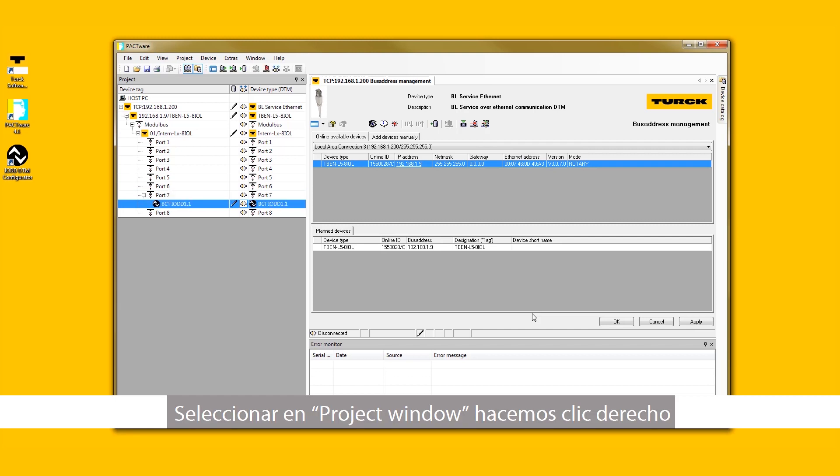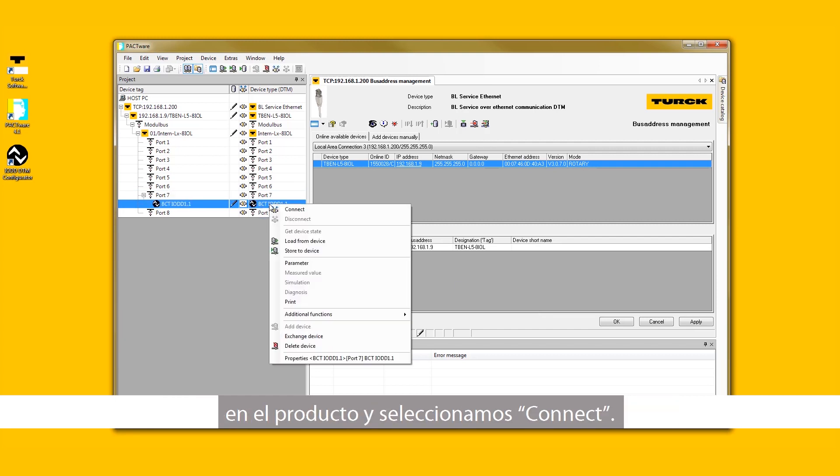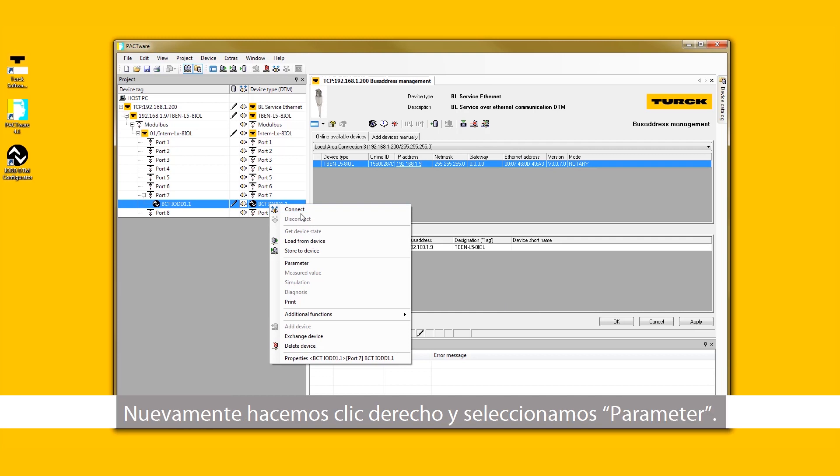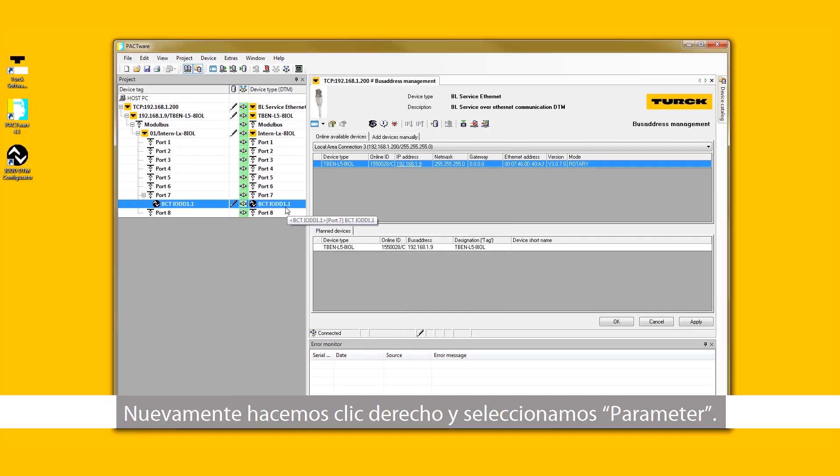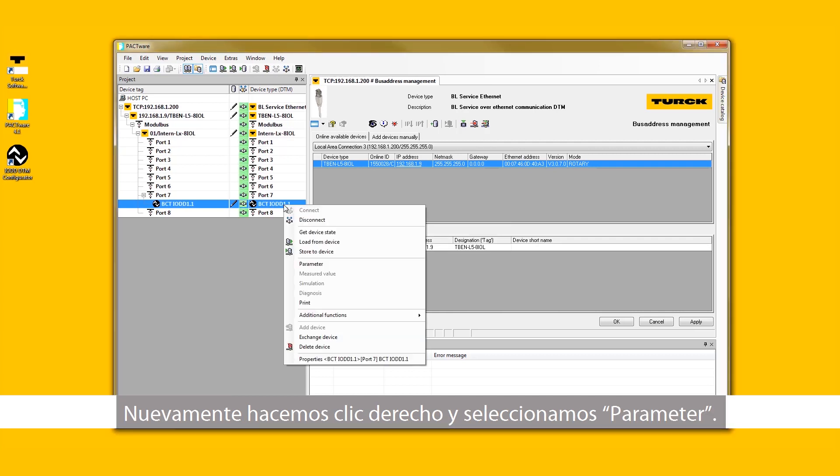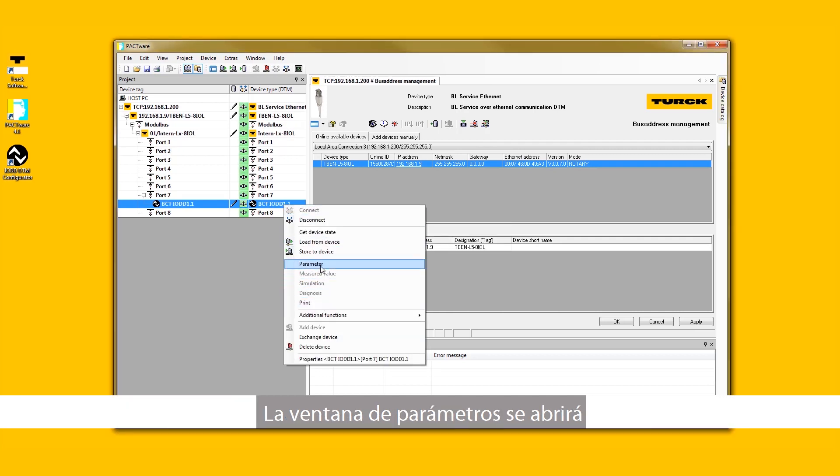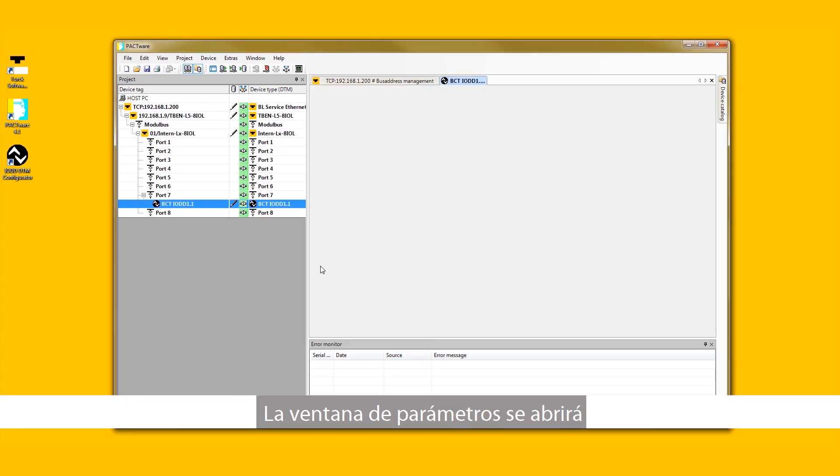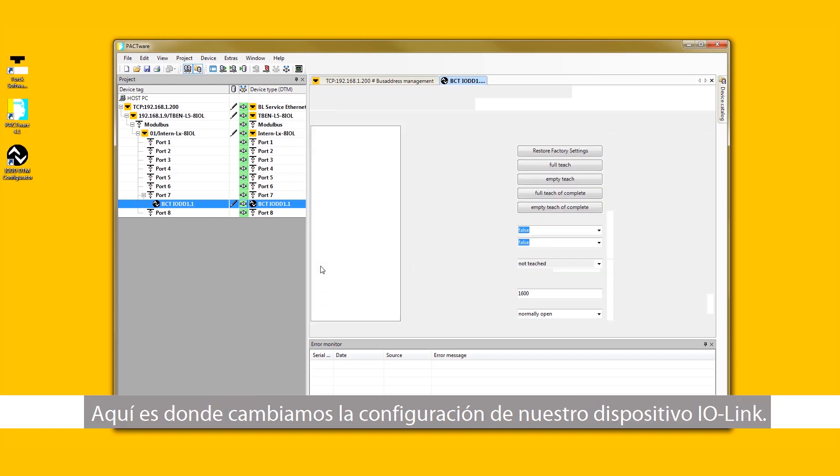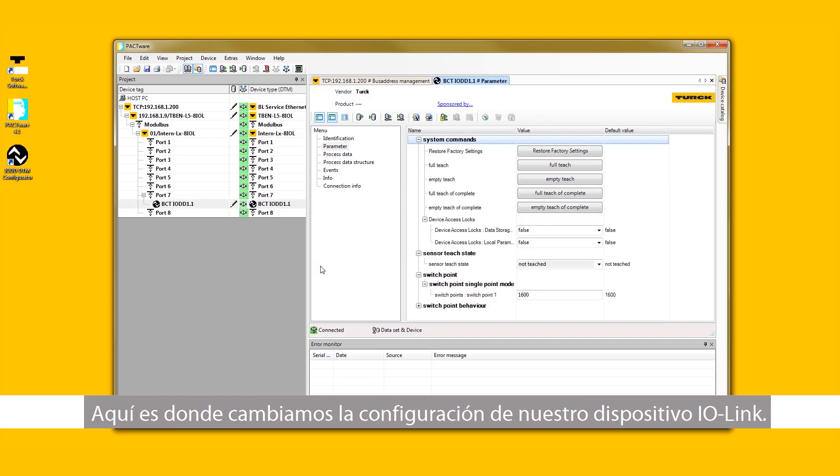In the Project window, right-click on the product and select Connect. Once again, right-click on the product and select Parameter. The Parameter window will open. Here is where we change the IO-Link device configuration.